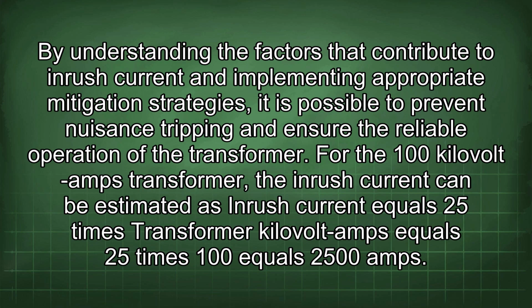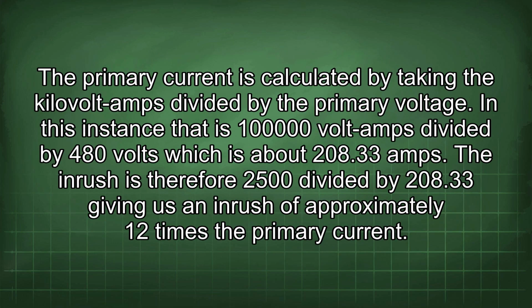For the 100 kilovolt-amps transformer, the inrush current can be estimated as inrush current equals 25 times transformer kilovolt-amps equals 25 times 100 equals 2500 amps. The primary current is calculated by taking the kilovolt-amps divided by the primary voltage. In this instance, that is 100,000 volt-amps divided by 480 volts, which is about 208.33 amps. The inrush is therefore 2500 divided by 208.33, giving us an inrush of approximately 12 times the primary current.